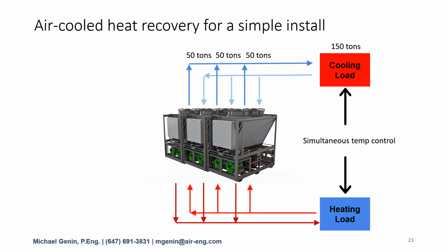There are also air-cooled examples as well. An air-cooled chiller makes this hybrid model very simple because the auxiliary heat rejection can be completely controlled by the chiller itself. There's also no cooling tower or condenser water piping. Since it's one packaged unit, with these chillers, all you need to do is bring your chilled water lines like any other machine and bring in your hot water lines like any other boiler. This makes for an extremely simple install and extremely simple controls, which are all contained inside the chiller. The chiller can alternate between generating hot water or rejecting heat out through its built-in air-cooled condenser.